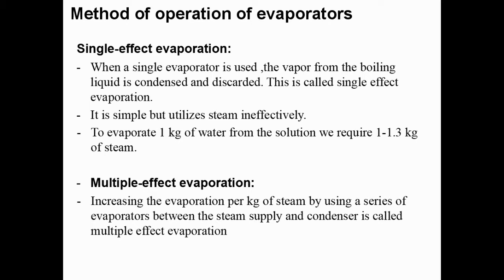To improve efficiency, we use multiple effect evaporation, which increases the evaporation per kilogram of steam by using a series of evaporators. In this case, the vapor coming from the top of the first evaporator is used as steam for the second evaporator, and the vapor from the second evaporator is used as steam for the third evaporator. With this method, we can save energy.